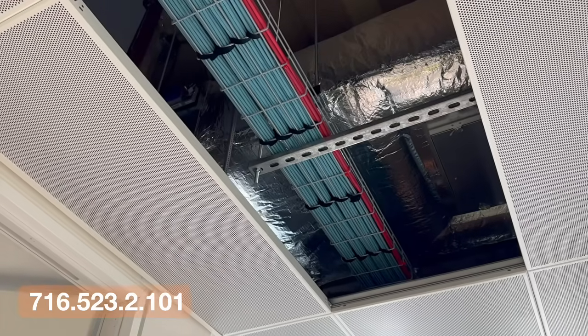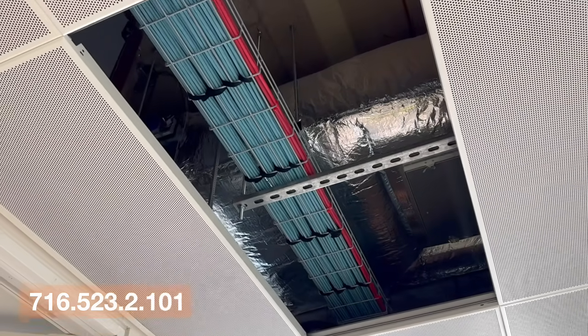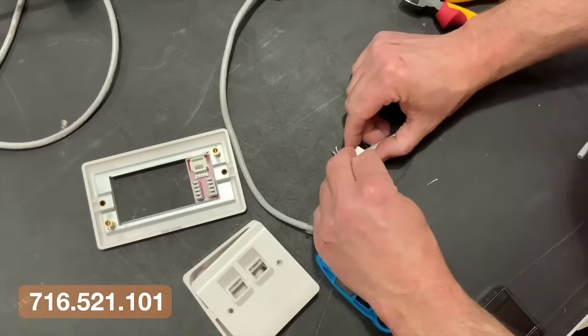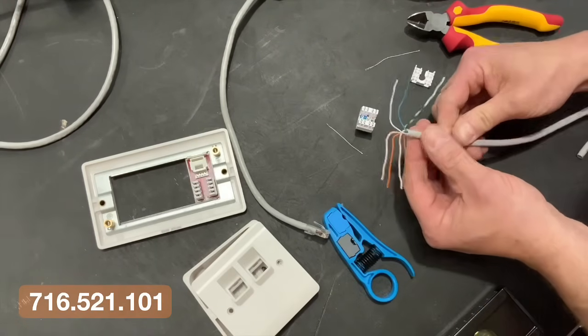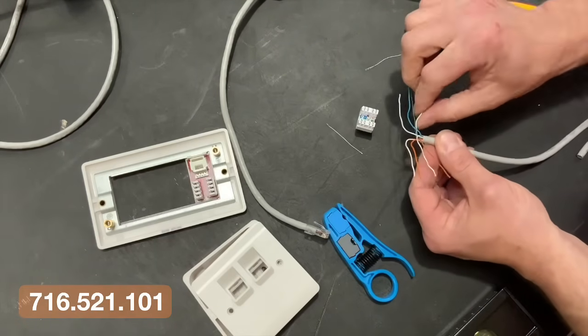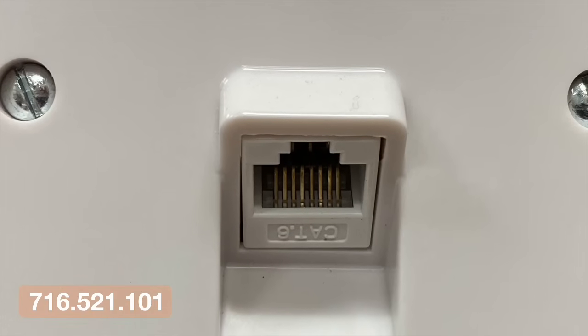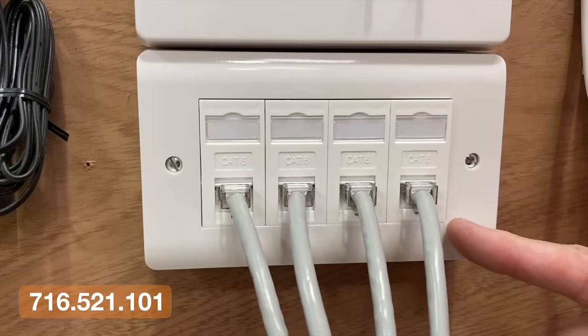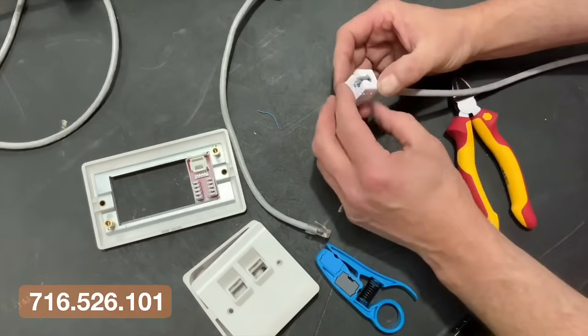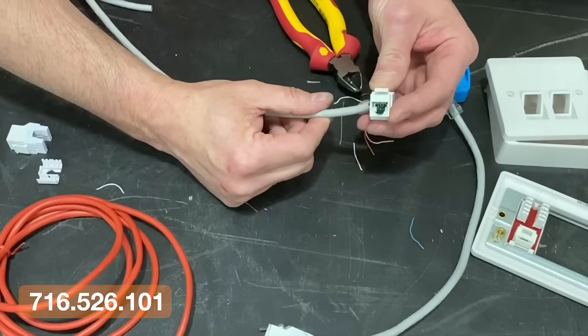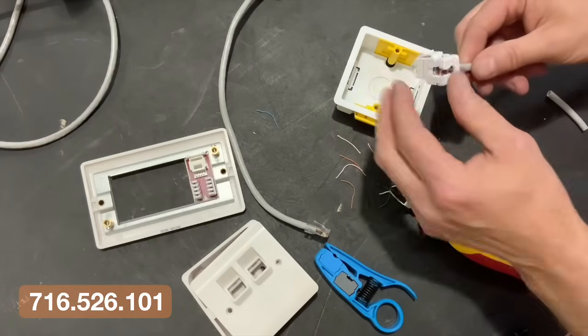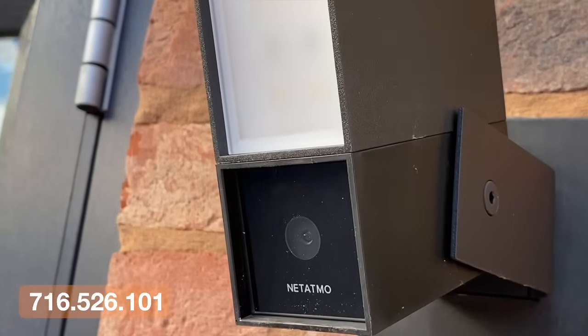Grouping, bundling, containment, all of these affect how the system behaves. Cable selection is also important. Regulation 716.521.101 requires cables to comply with recognized standards such as Category 5 or Category 6, and the same applies to the connections. Regulation 716.526.101 requires connecting hardware to be suitable for continuous current. So this is not just about making a data connection, it has to be capable of carrying power safely as well. There are also restrictions on where these systems can be used.